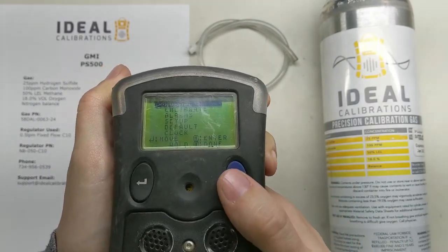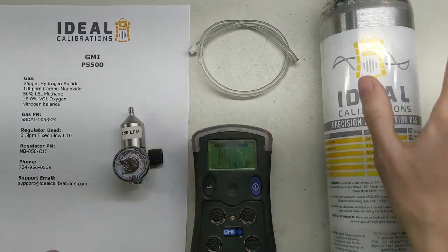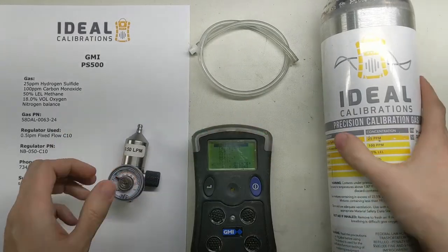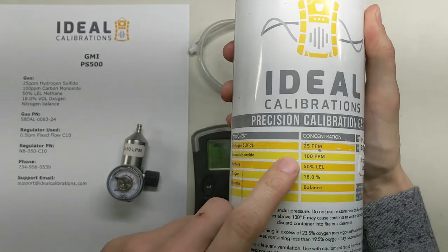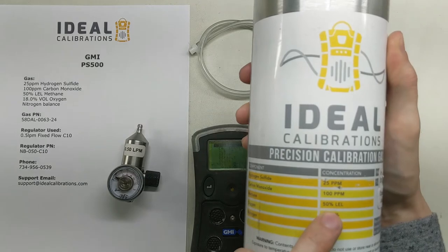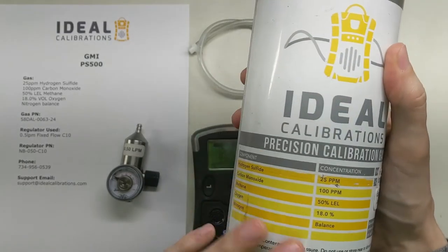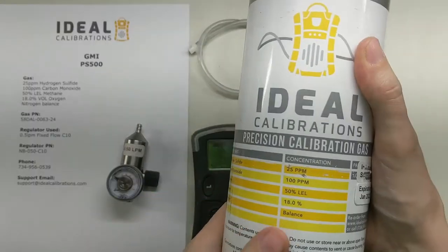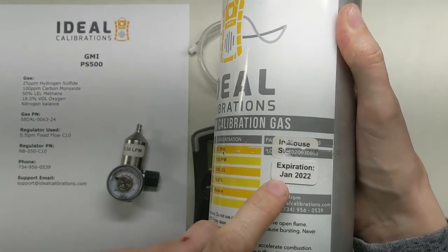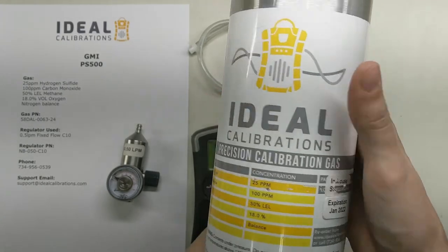Now we're on the main menu. Before we get into going through the menus, let's get our calibration gas and regulator set up. We have a 0.5 LPM regulator, and for calibration gas we have a mix of 25 ppm hydrogen sulfide, 100 ppm carbon monoxide, 50% LEL methane, and 18% oxygen. This is the recommended mix for this unit, though you can use any mix — I'll show you that once we get to the calibration. Also check that the expiration date is after today's date; we're in February 2021, so we're okay.